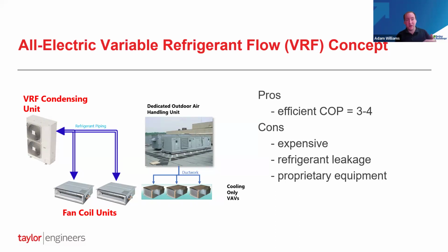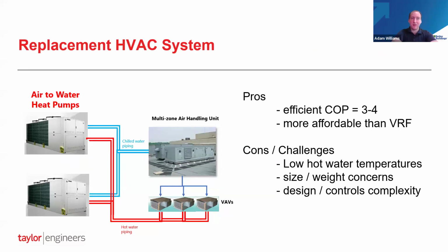The other concern that owners and operators sometimes have with VRF is that the manufacturer is providing the condensing unit, the fan coil units, all the controls associated with that, and you're kind of married to that manufacturer once you design it. You're dependent on that manufacturer many times for service, for TI retrofits, future modifications and changes to the system. So some owners aren't a fan of that. So anyway, this was looked at, but we didn't end up going with this. Let's go to the next slide and we'll look at the solution we did go with, which was air to water heat pumps. So these units pump heat from the outside air to your hot water piping, and they can run as an air-cooled chiller the opposite way, basically, where they pump heat from the chilled water to the outdoors.